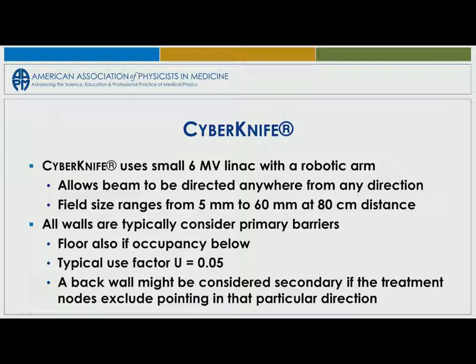If you've ever done diagnostic shielding, dental units have a use factor of 0.05. That's the same factor that we use for a CyberKnife. We assume that any point on a given wall will only be hit 5% of the time. So you basically take the equivalent of what you've got in a primary barrier and you average it out and spread it out over the whole wall, because the use factor is only 5% for any one point.